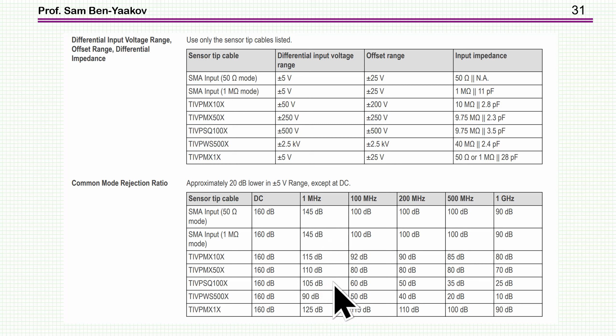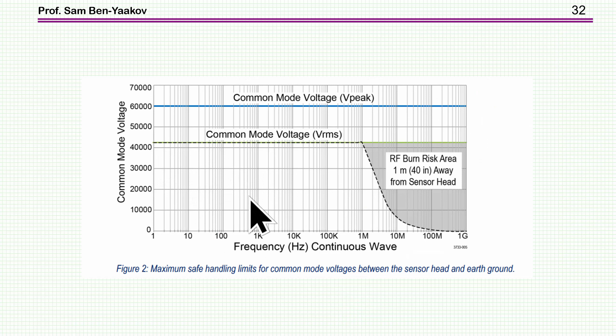And if I go to 1 megahertz, which we compared earlier, it really depends on the tips, but it can be something like 145 dB, 110 dB. We were talking about 60 dB for the medium type differential probe. So there is no question that this is really much. Now, as far as the isolation, this is fiber optics, so you can go up to 40 kilovolt between the tip and the base. That is, the tip can be 40 kilovolt referred to ground, which in some applications could be very important.